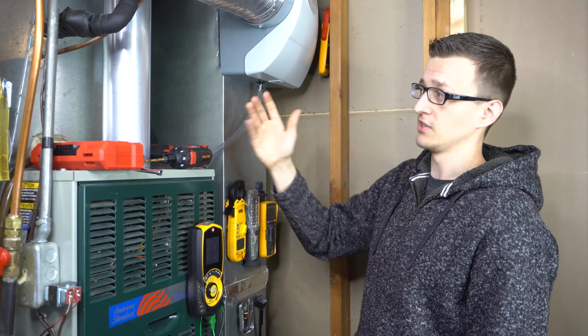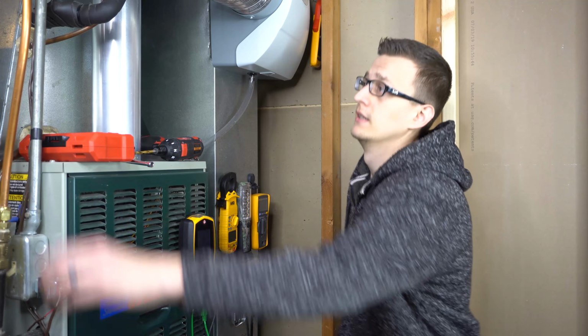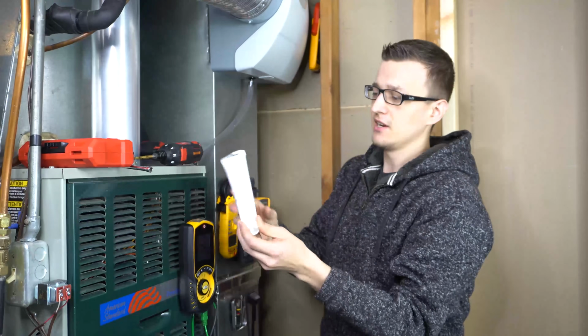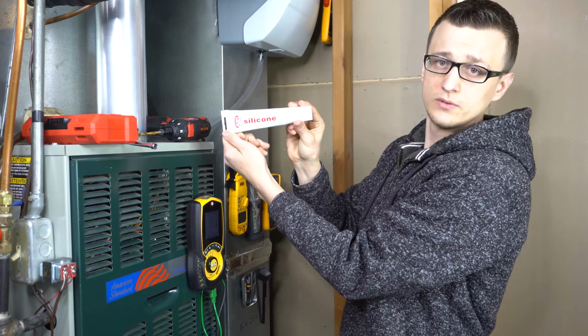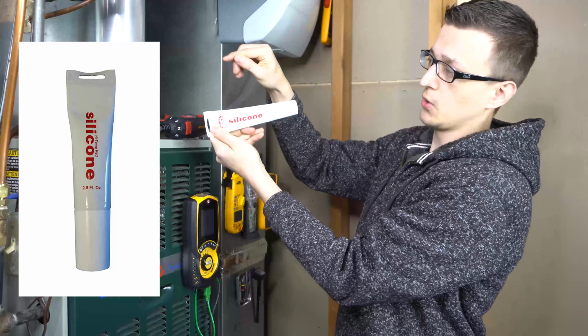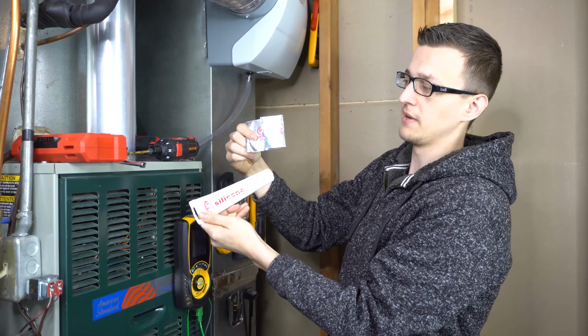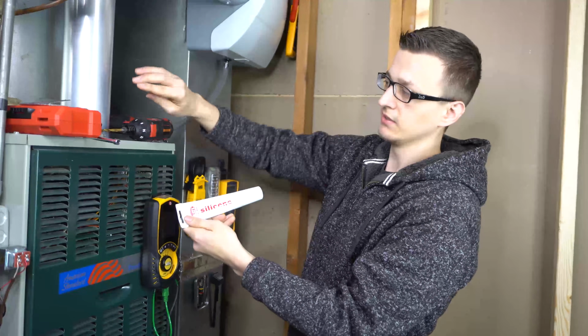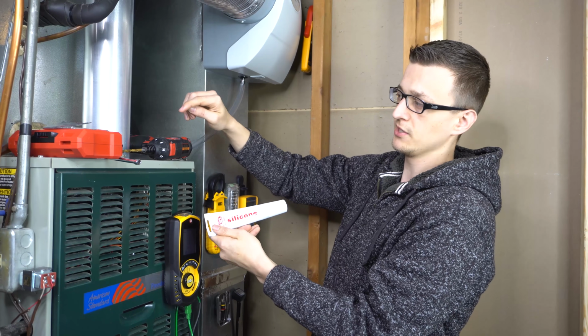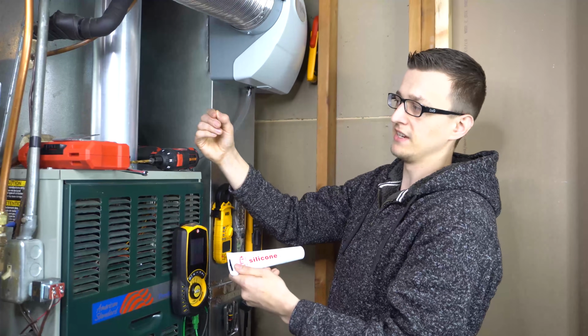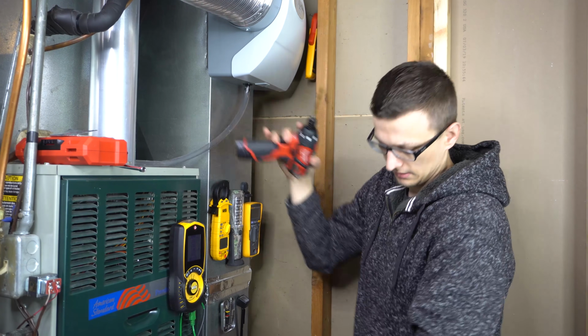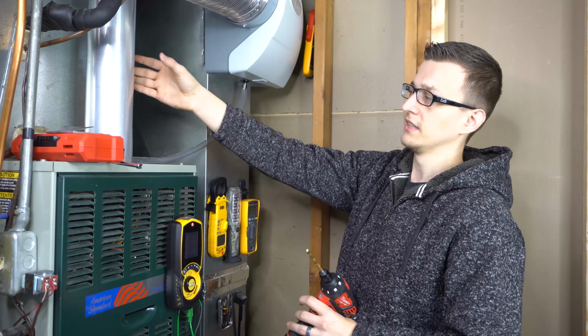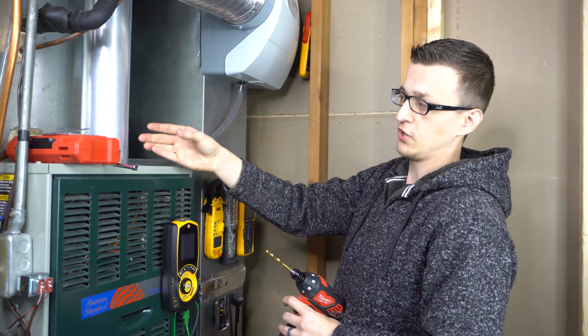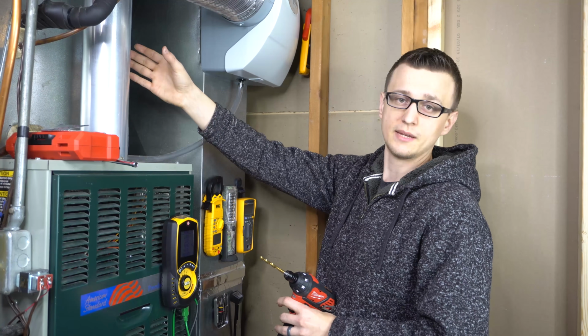And if for some reason somebody drilled a hole in it before you, the best way to seal that up would be with some high temp silicone. So just squeeze some silicone in there and then cover it up with some aluminum tape or some sheet metal tape. So type C single wall venting is okay to drill right into, but type B double wall venting is not okay. Luckily, most of those type B vents, they have an adapter on the bottom where it transitions from a type C into a type B.